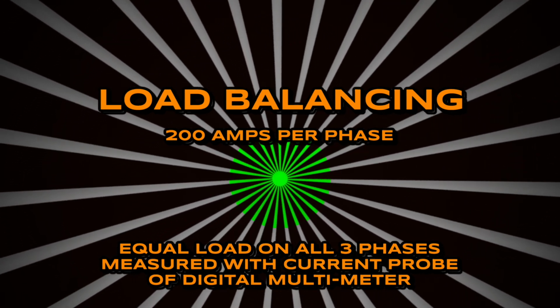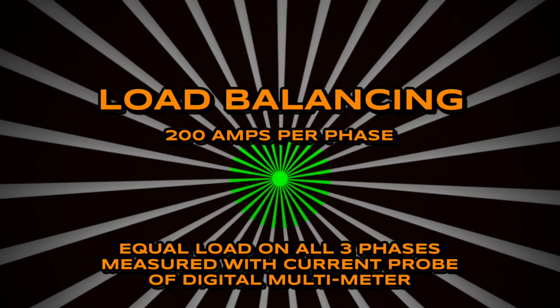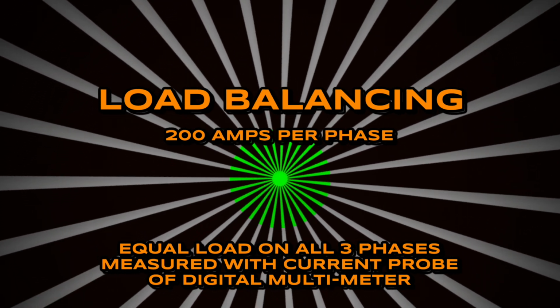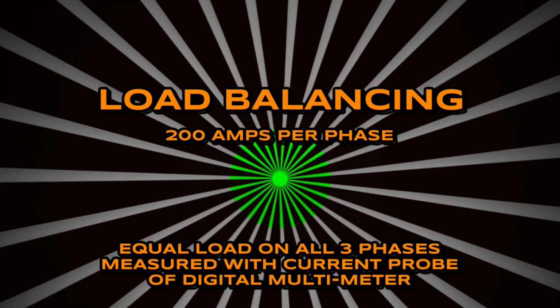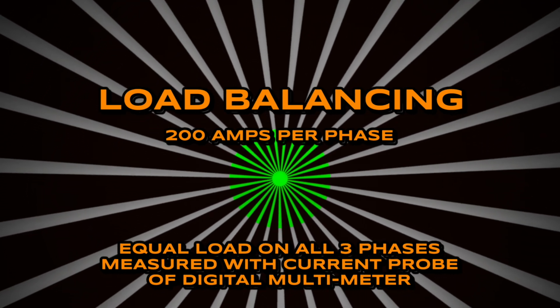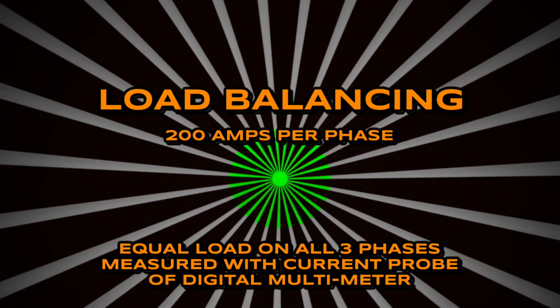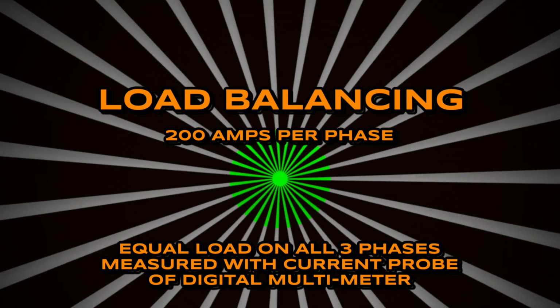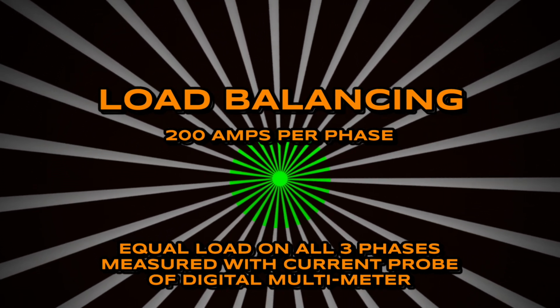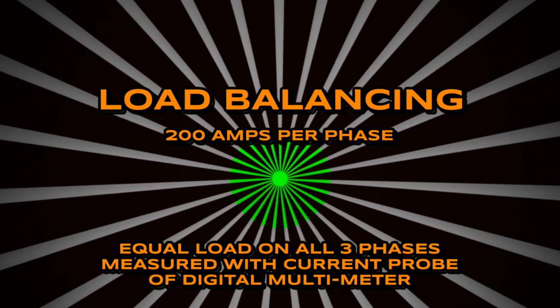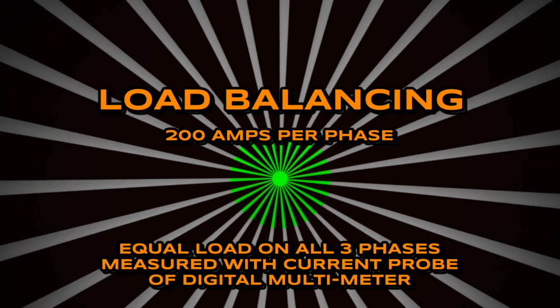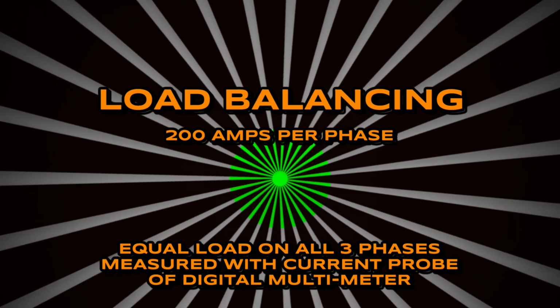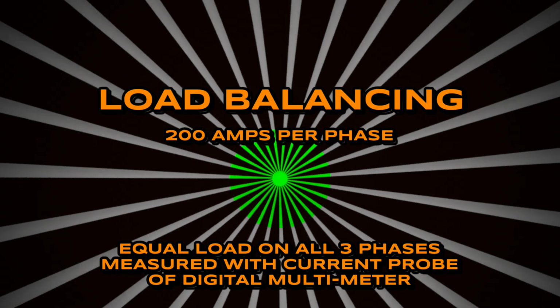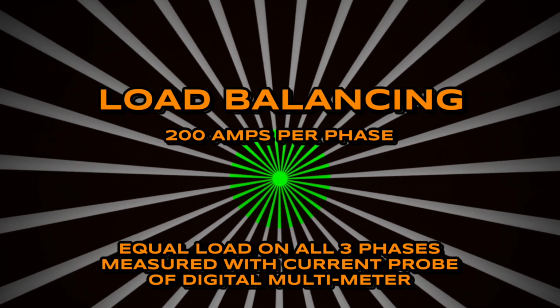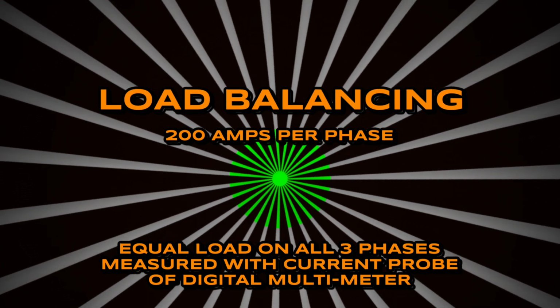The reason why, I can tell you from experience, is sometimes local services may have a weak fuse. It may say 200 amps on it, but the fuse may actually blow earlier. Knowing that your load is balanced helps in troubleshooting and also helps to explain why something happened to your artist or your production manager. Another reason is to help reduce wear and tear on equipment. As feeder heats up due to a larger current draw on it, voltage may actually drop on that phase.